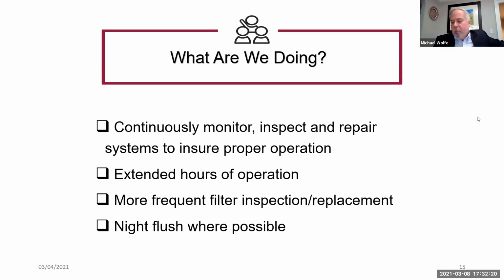So Joel, you had just a quick question. You have mentioned quite a few times that there's a minimum amount of air intake. Is there a percent that you could say of fresh air coming in that is the minimum? Yeah, generally, Mike, the minimum is 15% of the air coming through a system has to be fresh outside air. We currently have our system set at 20.